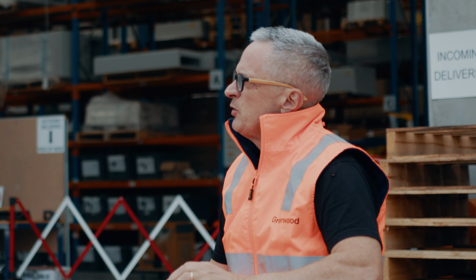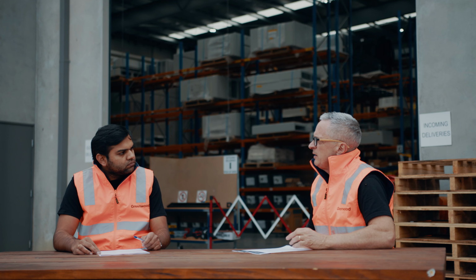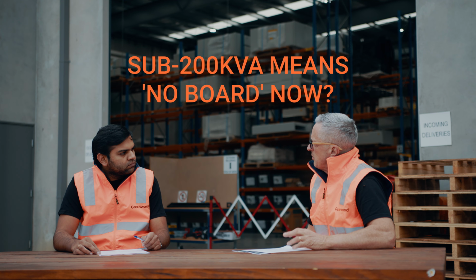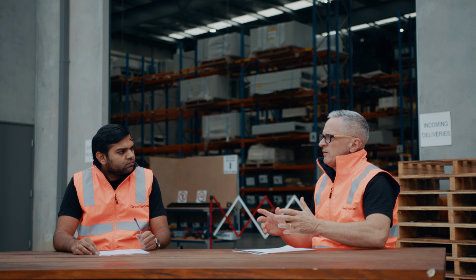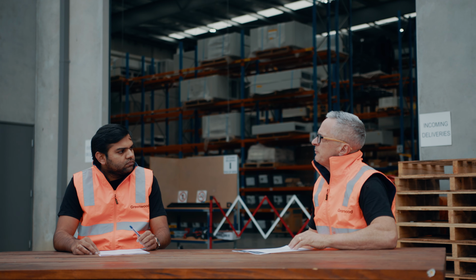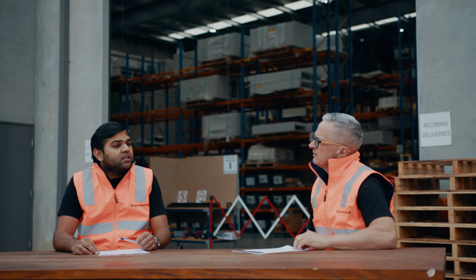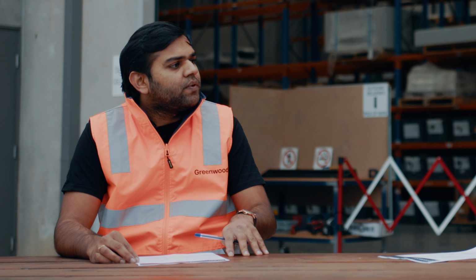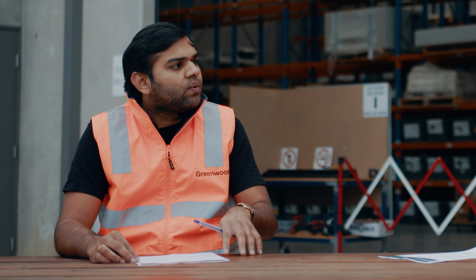Some people think a 200 and under kVA system doesn't require a board. That's a bit risky, isn't it? Yes, it is a risk, as some of the distributors still ask for the interface protection relay, which will be notified by the distributor during the grid application stage. So the requirement for grid protection is really still up to the DNSPs? Yes, you can say that, because from our analysis, we have found some of the distributors still require the interface protection relay.